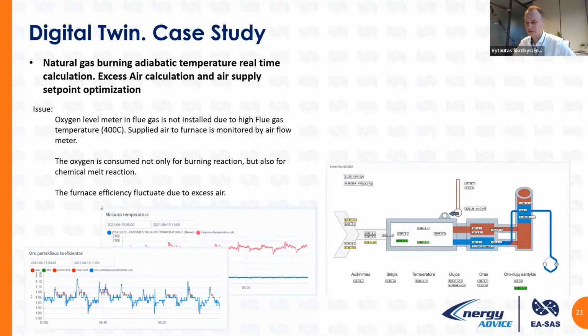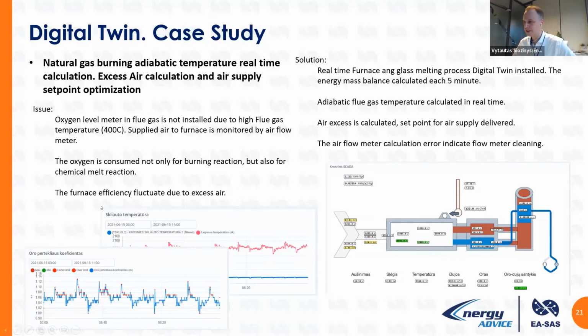And finally, before our solution, the client had to supply extra air to the furnace, and efficiency was fluctuating due to extra air, due to this energy and chemical process. And when we install a digital twin, we calculate each 5 minutes the status of a furnace, and we can calculate required excess air to the furnace, and we deliver set points, what should be the gas to air ratio at the controller, at the SCADA system, in order to have good chemical process and good furnace efficiency.